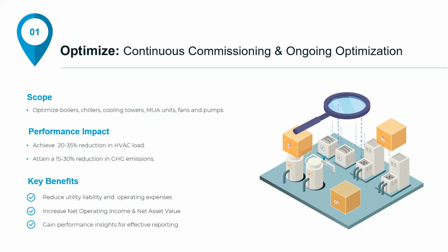In this case, the installation of smart controls gets us to a point where we deliver roughly between 20 and 35% reduction in HVAC load in the buildings, associated with 15 to 30% reduction in greenhouse gas emissions, because a lot of the savings come from reduced gas usage in the wintertime. We're going to get into some more details on how that happened.